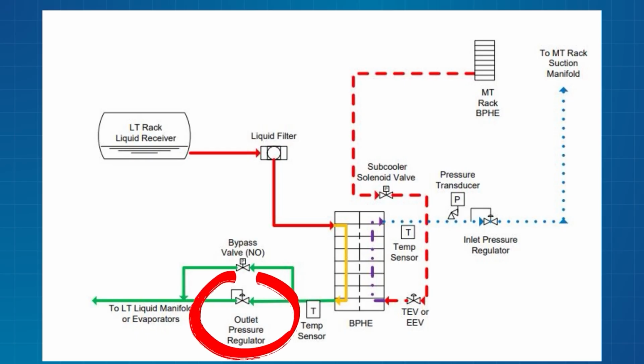Yeah, but if your load reduces, all right, so I may hit that low pressure anyway, is your point, right? Yeah, I will. And when it's cold outside, and I've got light load, can my discharge pressure fall? Yes, it will fall, of course, right? All right, my subcooler does the exact opposite. For every degree that I take out, my valve gets bigger and bigger, right? More efficient. All right, the reason why this outlet pressure regulator is right here at my subcooler is because they're gonna work together.